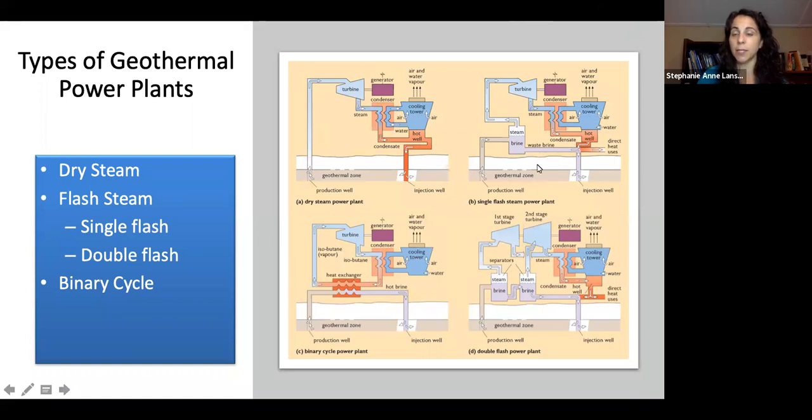In a single flash steam power plant, as pressure releases, steam is released and goes through the turbine. The brine comes down and goes back through the injection well. We have a cooling tower and can use some water with heat directly. With a binary cycle, the brine stays in one loop. We use a heat exchanger and isobutane for the steam vapor instead of water vapor, with a cooling tower and injection well.